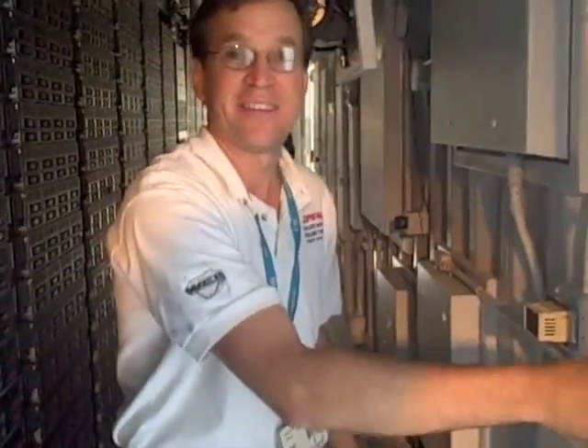Normally they use 45-degree, really cold water. Imagine the energy savings if you could go home and turn down your thermostat — instead of making it 45 degrees, you could make it 65 degrees. And by closely coupled you're saying they're next to each other? They're next to each other. In a traditional data center the air conditioners can be as far as 40 feet away, so the equivalent would have to push really hard — you can imagine the energy it takes to push all that air around. And because they're not closely coupled, some of the hot air from the back of the servers could pull around the front, so in order to prevent that they have to push even colder air. Here we put it all together and we're seeing a 50% increase in efficiency versus traditional data center deployments.